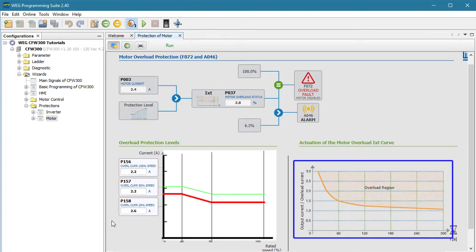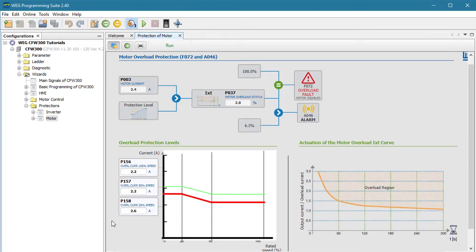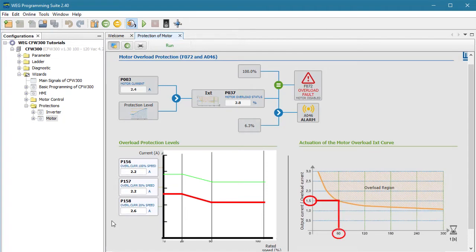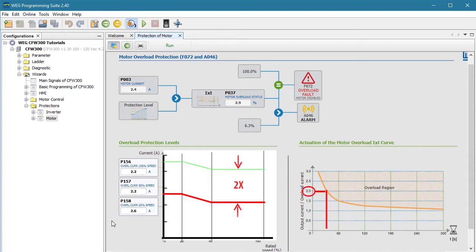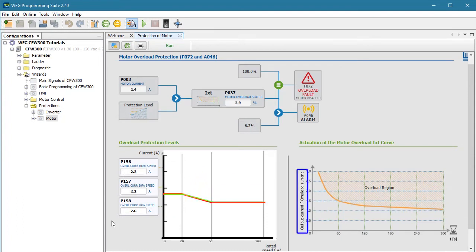The IXT function converts that integrated sum to a percent overload using some typical motor heating models. This curve over here shows you the result. For example, if the output current is 1.5 times the level we specified for the overload, a fault will occur in about 60 seconds. If the loaded current is double what we expected, the overload will occur in about half that time. And if the actual current divided by the level we specified — this ratio — is less than 1, we'll never get an overload condition.